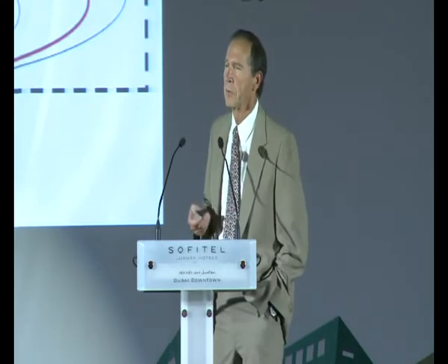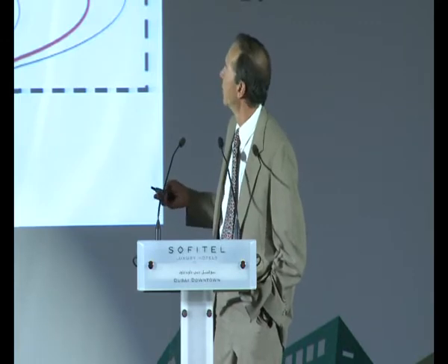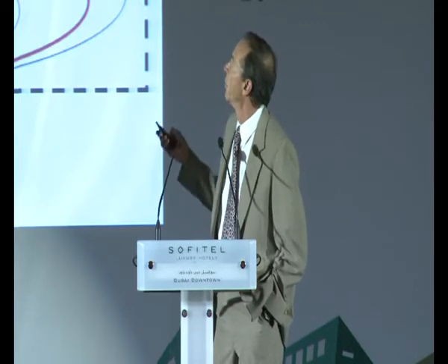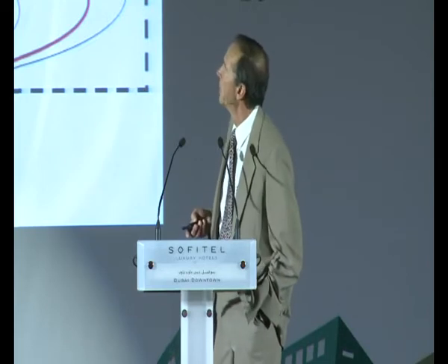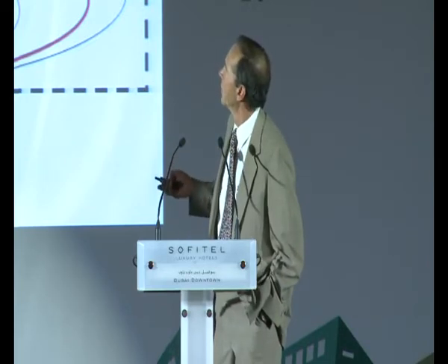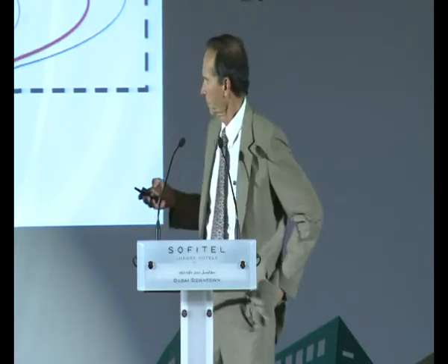The base case, which really helps us understand: we've got a leak source. We've got a room that is being supplied by that leak source. This represents a direct expansion kind of system. The refrigerant is leaking out and ultimately would lead to the RCL calculation, in other words, 25% of the room. So we're examining the time at which the refrigerant disperses and goes into the room.